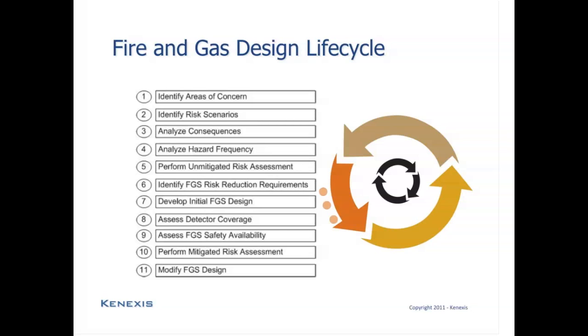Considering all of that information, you'll perform an unmitigated risk assessment, determining what the risk is with the situation as it is before the fire and gas system is applied. If that risk is acceptable, then no system will be required and you can stop at that point in the safety life cycle. But if the unmitigated risk is not tolerable, then you'll need to proceed on to the next step of the safety life cycle, which is identifying fire and gas system risk reduction requirements. So you'll determine what type of fire and gas system equipment you're going to need.